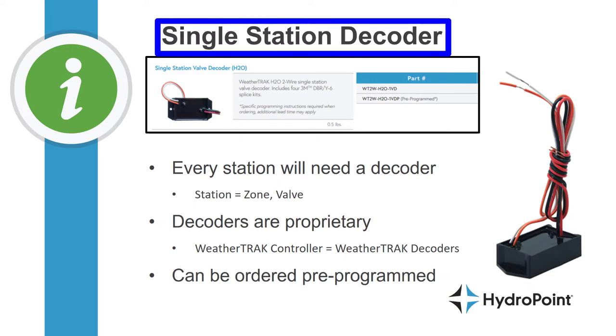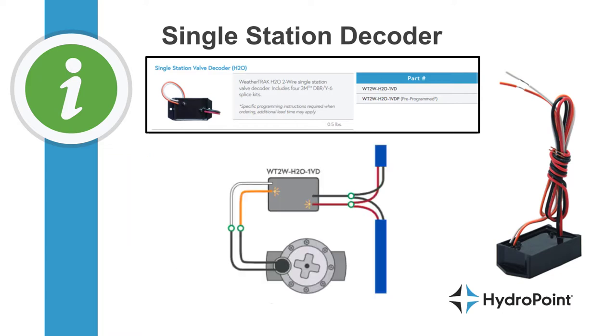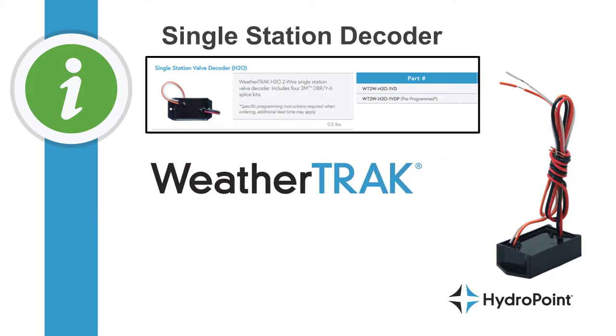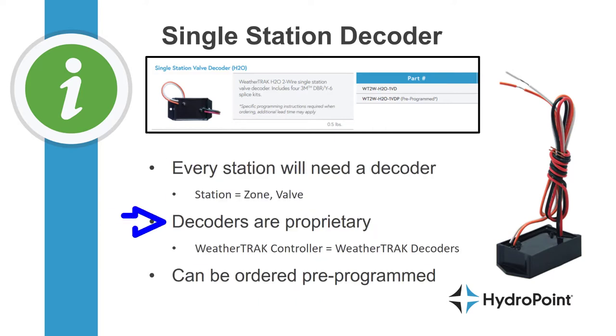Let's begin by discussing the single station decoder, which is by far the most common decoder you'll use on your WeatherTRAK H2O two-wire system, because every station, zone, or valve on your system will need to be accounted for by a decoder. The single station decoder is designed to handle one valve, wired between the two-wire path and the valve in the field. Two-wire decoders are proprietary, so the decoders match up to the control system. This means if you're replacing an existing system with a WeatherTRAK H2O two-wire, you also have to replace all existing decoders, and when installing a WeatherTRAK controller you also need to install WeatherTRAK decoders on every station.